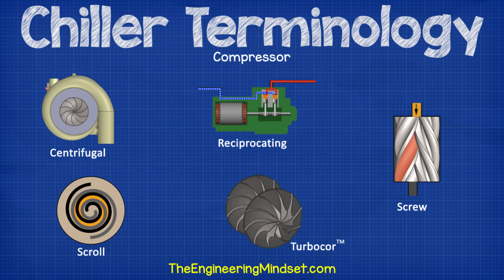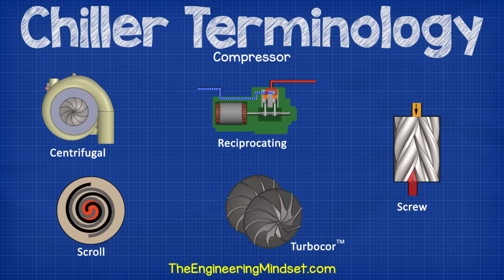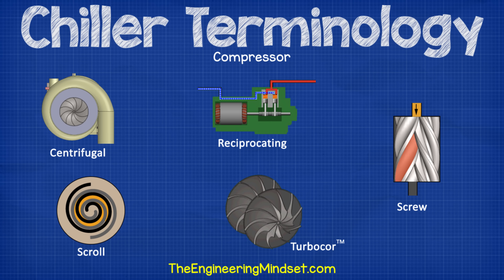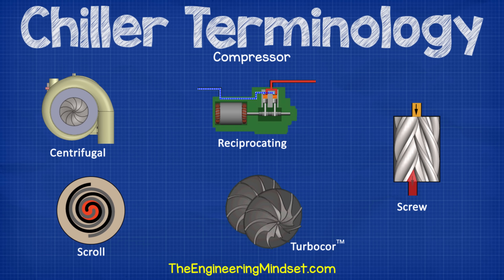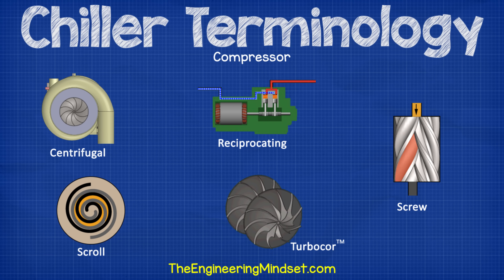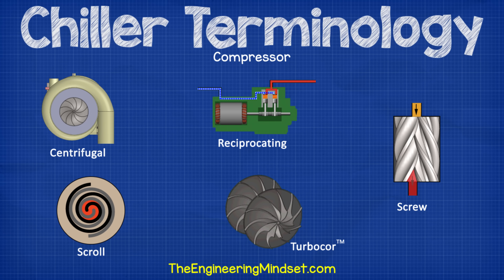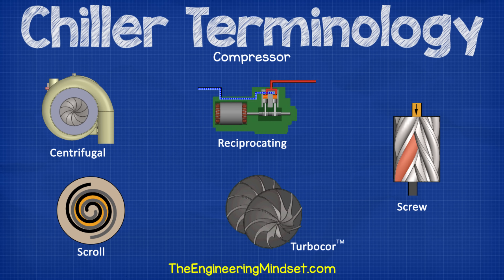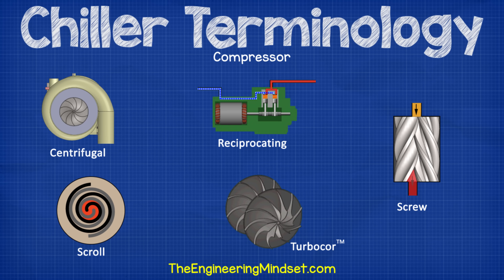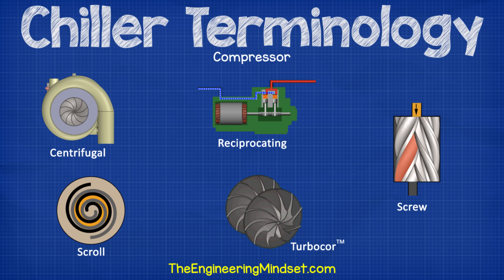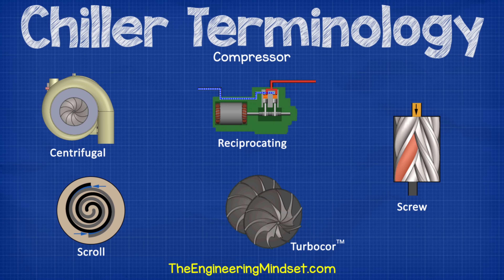Compressor. This moves the refrigerant around the chiller to collect the unwanted heat from the evaporator and move it over to the condenser. Some of the different designs you can get for chillers are: centrifugal type, which uses a rotating impeller to induce a centrifugal force on the refrigerant; Turbocor, which is a more advanced variation of the centrifugal type using two small rotating impellers; screw type, which uses two helical rotating screws to compress the refrigerant; scroll type, which uses two spiral discs — one stationary and one rotating; and reciprocating type, which uses pistons and cylinders to compress the refrigerant into a smaller volume.